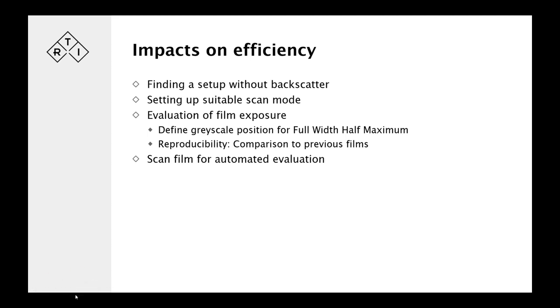And these things are quite important, I think, because you have a risk, especially when you have narrower beams, 10, 20 millimeters. If you have an overbeaming of only 2, 3, 4 millimeters on each side, that's a substantial amount of overexposure.